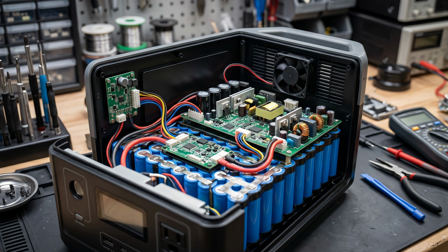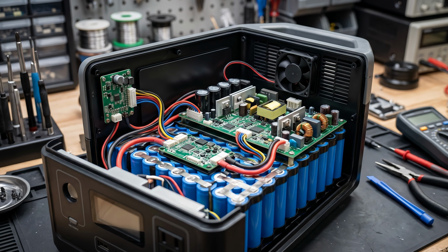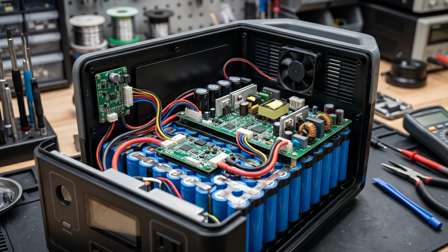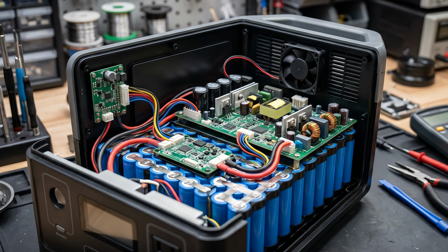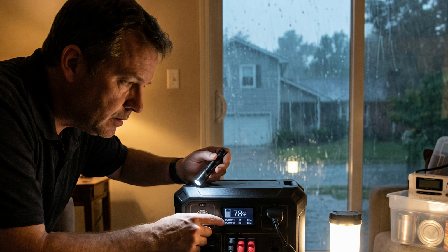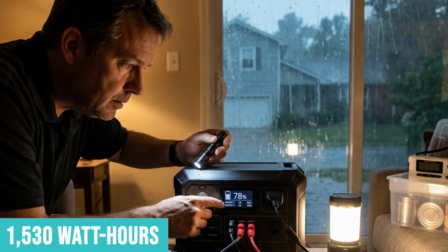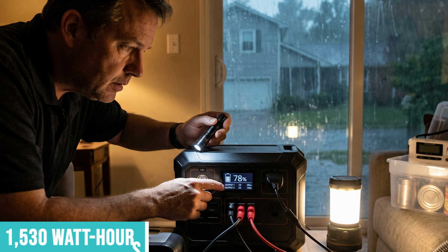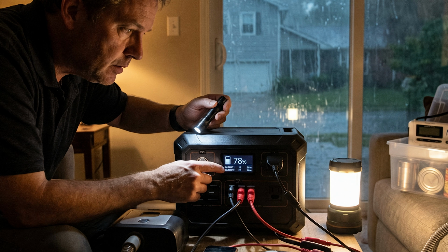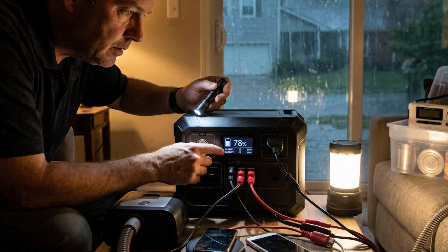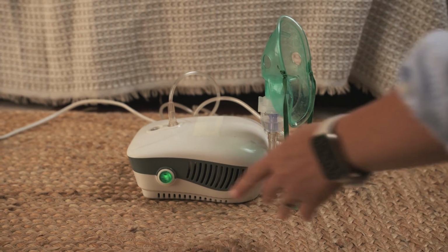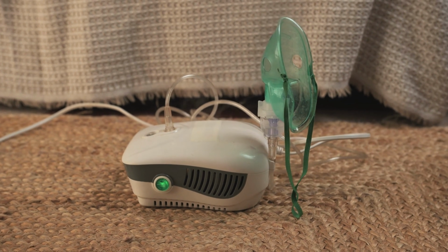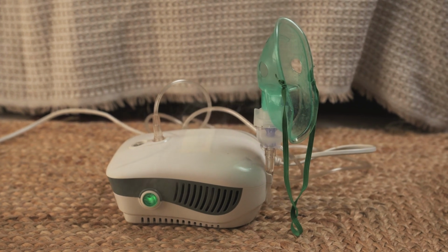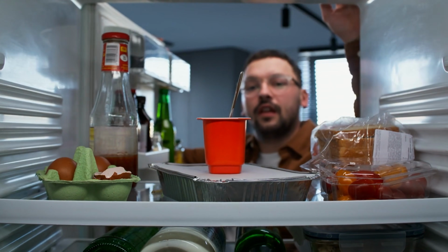Run the actual math. 2,000 watt-hours times 0.90 for the BMS buffer times 0.85 for inverter efficiency gives you 1,530 watt-hours of true usable output. You're getting 1,530, not 2,000. That's a 23% shortfall. If you're running a CPAP machine or keeping food cold through a 4-day storm, that gap is not a footnote. It's the difference between making it through and not.